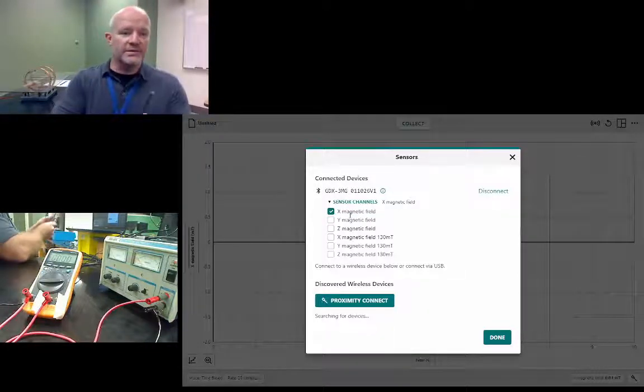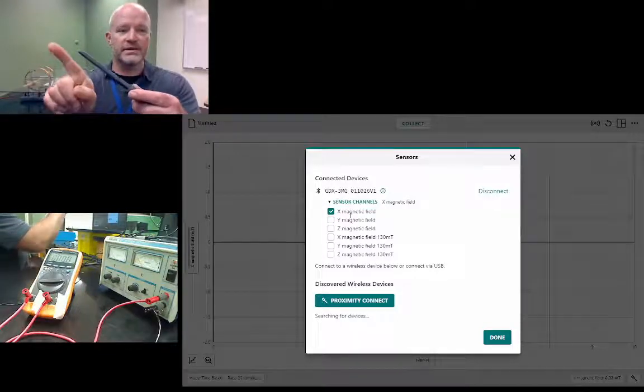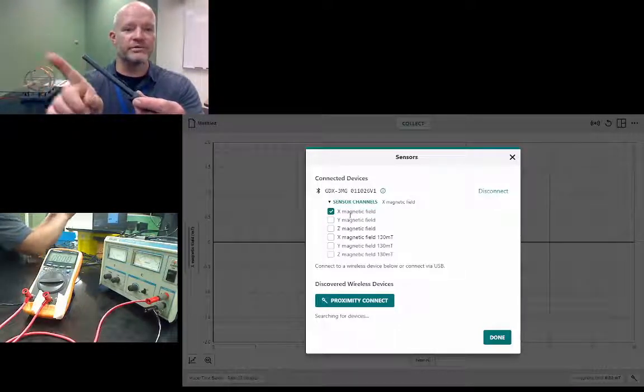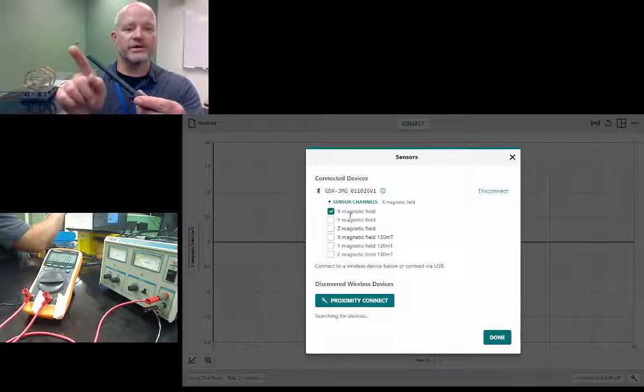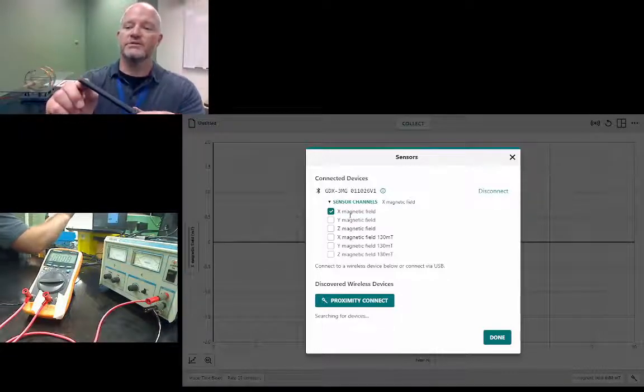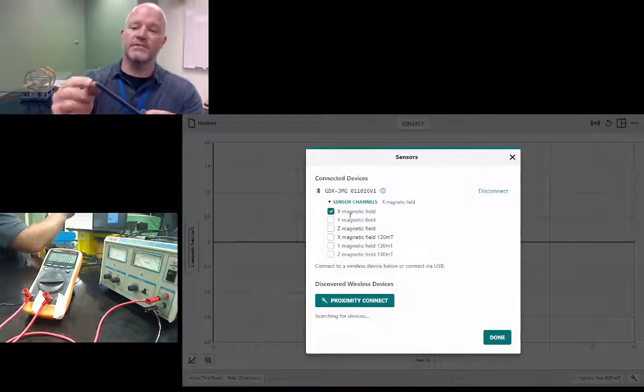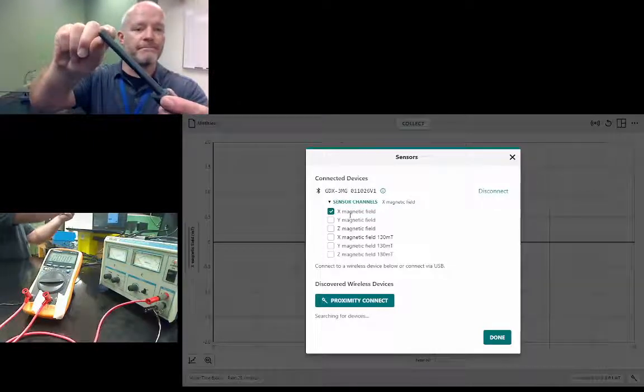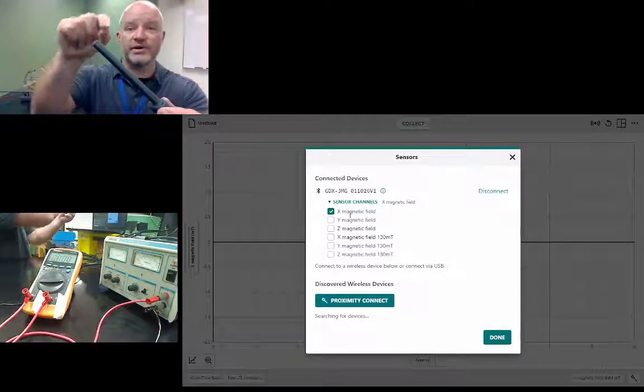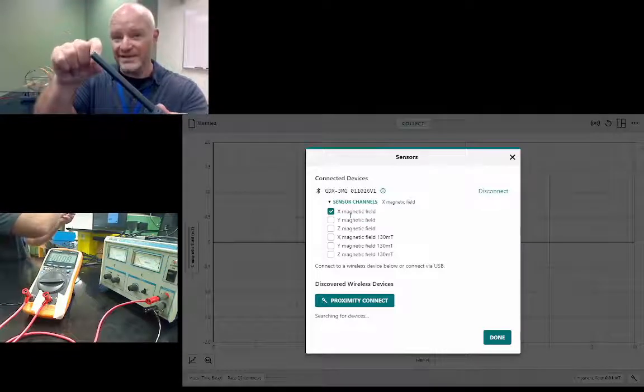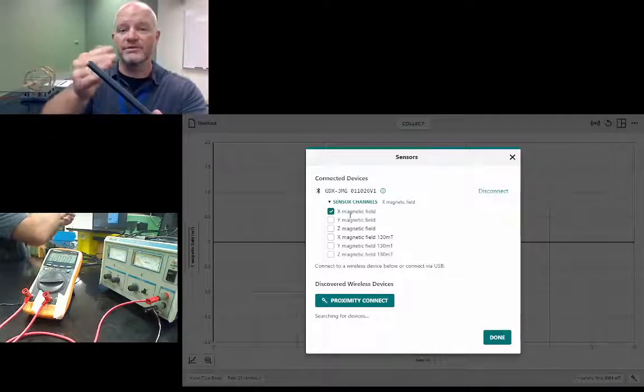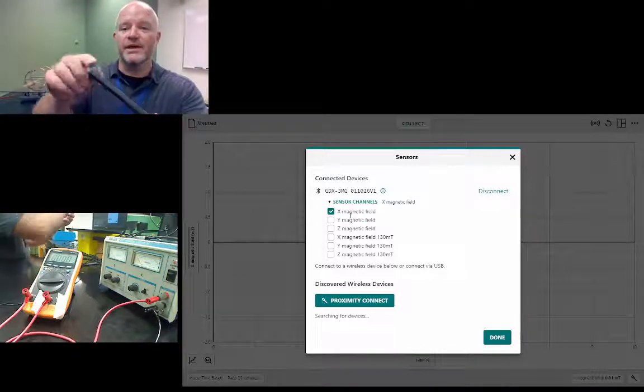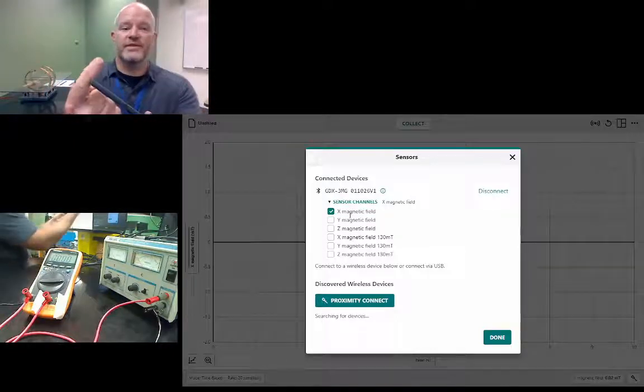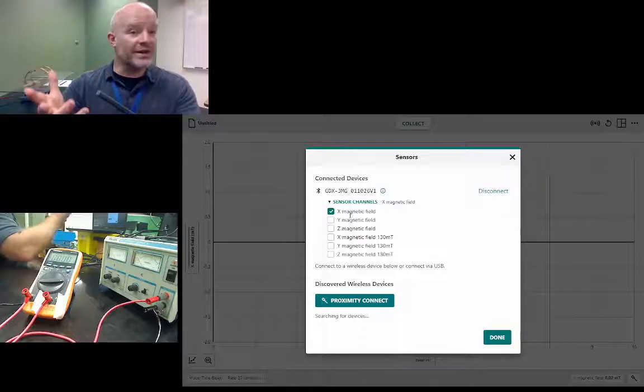The X direction is coming right out of the probe at the end of the tip here, so that's the X direction. There's a little dot on the side marked with a Y. The dot is where the probe sensor is actually located, just a few millimeters behind the tip, so that's the Y direction. The Z direction is coming out perpendicular to this top face. So it's a 3-axis probe.